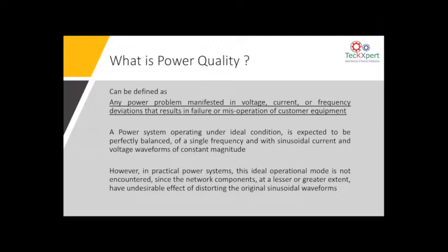That means any problem manifested in voltage, current, or frequency deviation that results in failure or misoperation of a customer's equipment can be named as a power quality problem. But that's an ideal scenario, to have a perfect sine wave. In a normal practical system, you never get a perfect sine wave, which is always going to be influenced by the various network equipment. You have various power electronics, transformers, capacitor banks, the whole lot of system components, which is not going to make sure your perfect sine wave is all throughout the network.